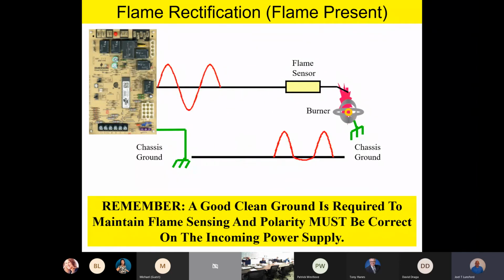We got a question. Sure, come on. Does the process get affected at all if the house or breaker box itself isn't properly grounded? That's an excellent question. Yes, it can. To expand on that, the furnace has to have a good solid ground where it's actually located, but that ground has to be a really good solid ground all the way back to the power panel and then down to earth ground.